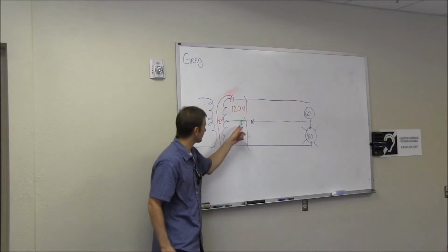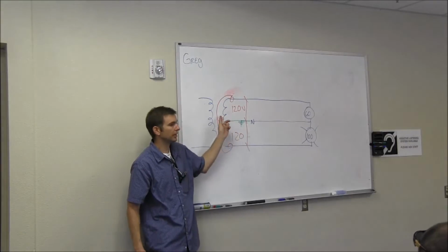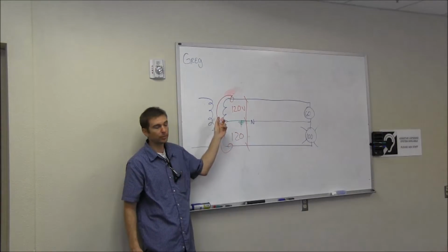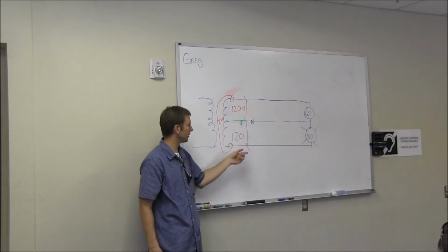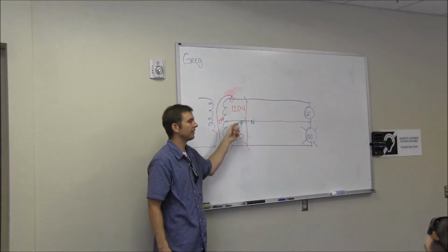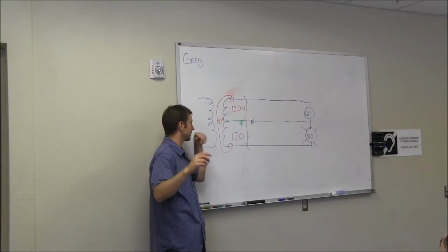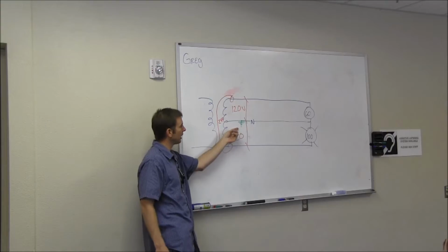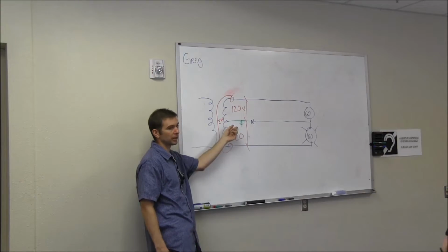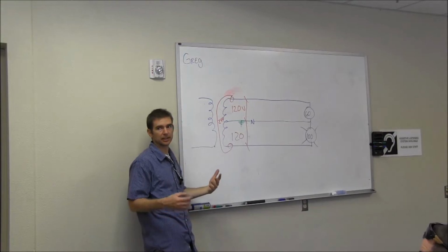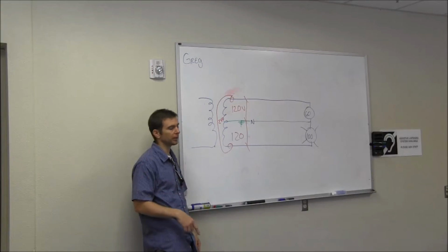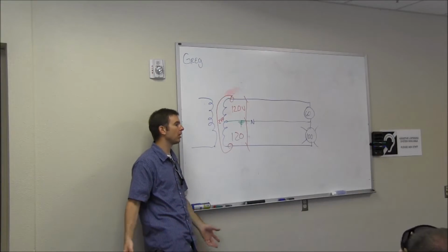What I've done here is draw the ground symbol. The center tap of your transformer is always going to be bonded to earth. So you have on your transformer somewhere, it's bonded, and then you're going to have a ground rod, or a grounding electrode conductor coming out, connected to your building steel, or your Ufer ground, ground plate, ground ring, or maybe all of the above.